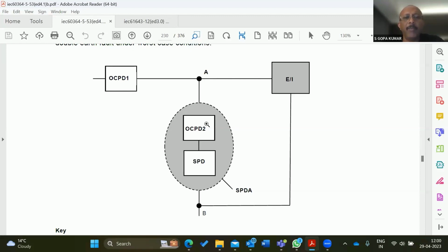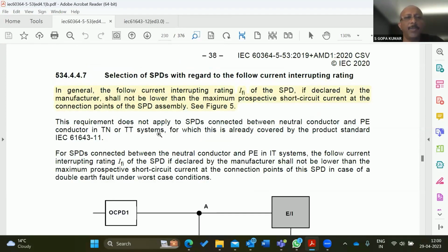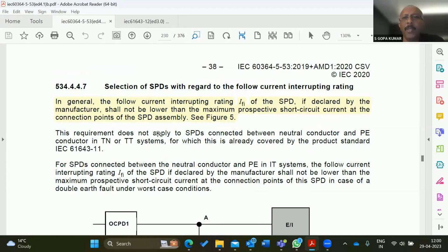The combination of the SPD and the 500 amps fuse together can handle only, sometimes, 20 kiloampere short circuit current. And if you connect this SPD and the fuse in your panel board at the incoming, where probably the short circuit level is much higher, let's say 50 kiloampere, we are actually risking the whole panel. So the safety is gone. This is a very important subject which you should take care of. That means the person who is selecting the SPD has to be technically knowledgeable to do the job.